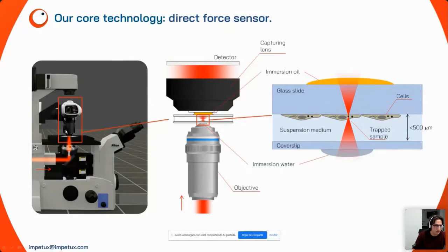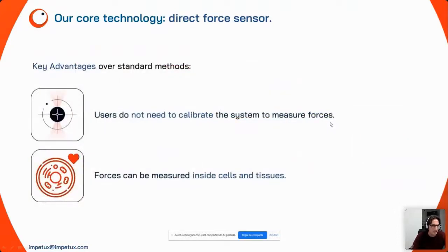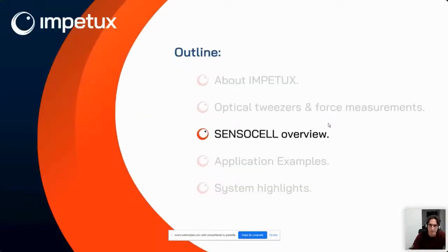All transmitted light is captured by our first sensor using a condenser lens, and the light is brought to our detector at the back focal plane. This detector analyzes the light patterns, giving a direct measurement of changes in light momentum and therefore a direct measurement of force on the trapped object. The key message is that users never need to calibrate to measure forces, and these forces can be measured inside cells and tissues.